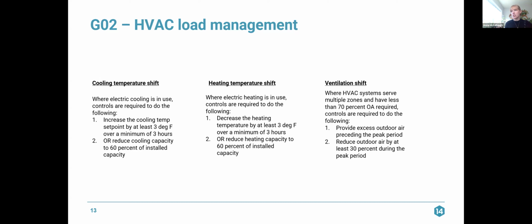And then a ventilation shift, and this one starts to get a little bit difficult, applies where the HVAC systems serve multiple zones and have less than 70% outdoor air required. So you can't do this for a DOAS.